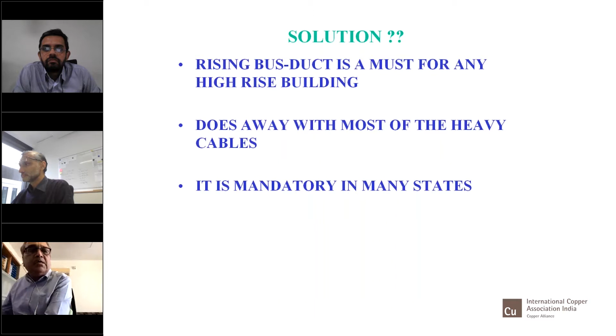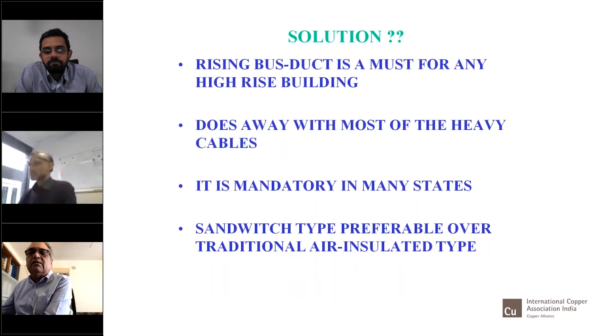We should prefer sandwich type bus ducts, where the chances of failure between conductors are less, and these occupy much smaller space. Sandwich kind of bus ducts can be managed with a much smaller size shaft going all the way.